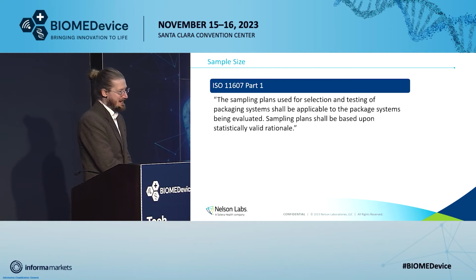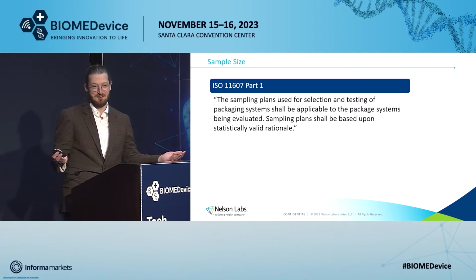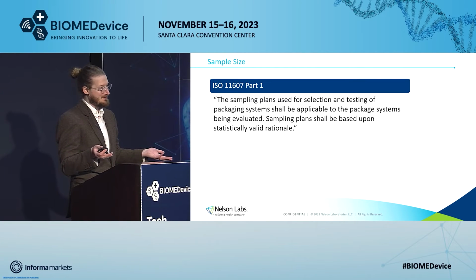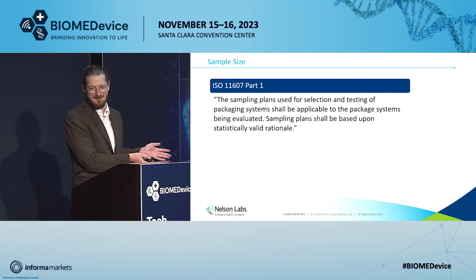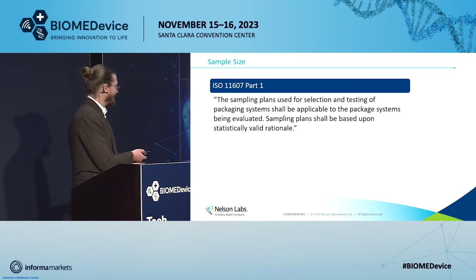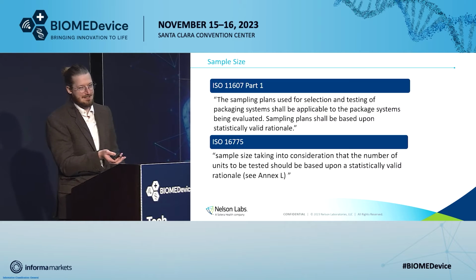I think sample size is probably one of the top questions that I get asked: how many samples do I submit for a package validation? And unfortunately, there's no clean answer. The answer is statistically valid rationale, which isn't very helpful because we like to have that easy number to hit. ISO 16775 more or less says the same thing.